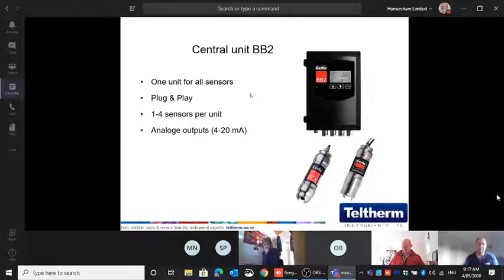This is the controller, how it looks. So we have a BB1 and a BB2. The BB1 can take one sensor, the BB2 can take up to 4 sensors. What the unit basically does, it just takes the sensor. You can control the cleaning with the unit, the 4-20 milliamp output of the unit, you can set that. And for calibration, you basically use the controller as well. So mainly, if we do the commissioning and we come on site, that is where we sit, and that's what I show you, the controller. We don't really touch the sensors anymore. We don't really have to.